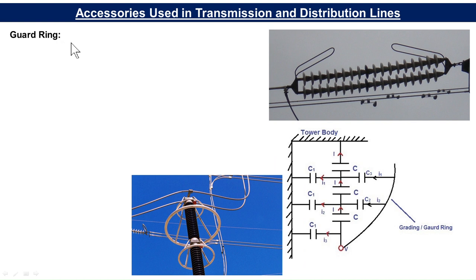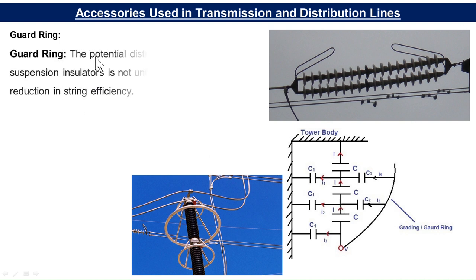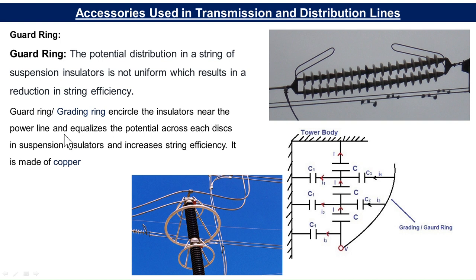Then there is the grading ring. These are grading rings used in transmission lines, and these are grading rings used in substations. The potential distribution in a string of suspension insulators is not uniform, which results in a reduction in string efficiency. The grading ring encircles the insulators near the power line end and equalizes the potential across each disc in the suspension insulator, thereby increasing the string efficiency. It is made of copper. You may have studied string efficiency problems in your BTEC diploma course.